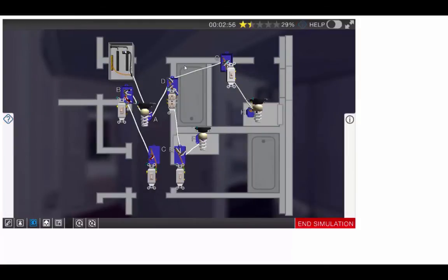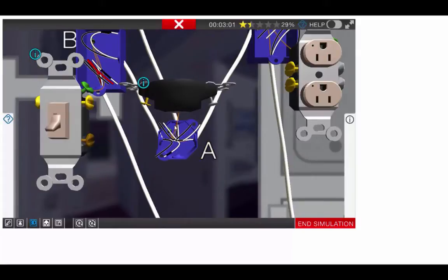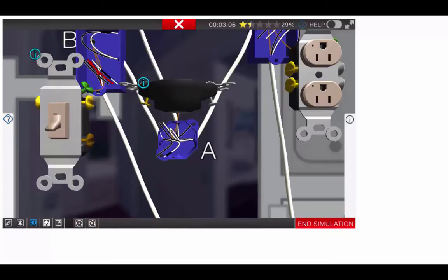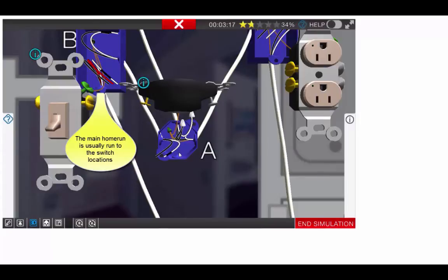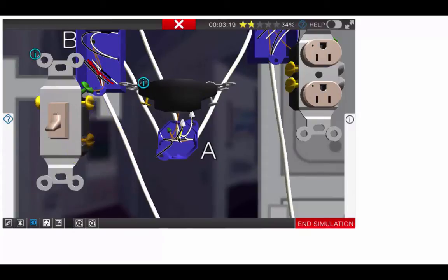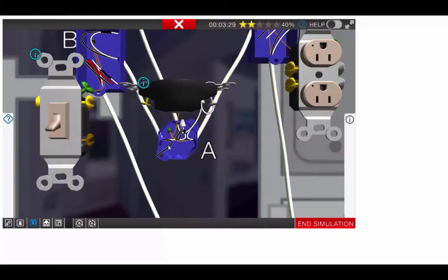So we'll start at box A. At box A, we will start with our neutrals. Our ground's already made up. That's the first thing I do when I'm wiring in a home. We'll make up our hots from the panel and going through to the other receptacle. Now remember, we re-identified our white as a hot wire. So we're going to also put that underneath the hot in box A. Now, we'll need to put a pigtail to the light fixture for the neutral. And our hot, coming from our 3-way, will go to the light fixture.